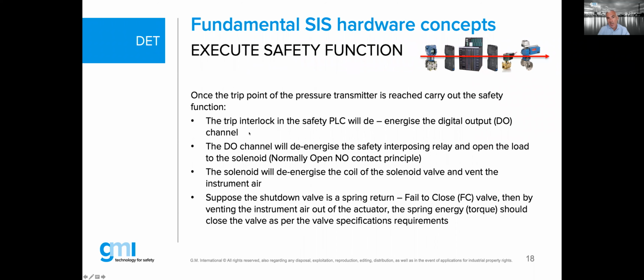Execute the safety function. Let's come to the bottom here, the energized to trip. We have to measure something and we have to shut down. Let's make this a simple example. That means measure something; that will be measured here in the interlock. It's somewhere in the safety PLC. Once your trip point has been reached, or gone through, that is where the final element needs to do the right function it has been designed for.